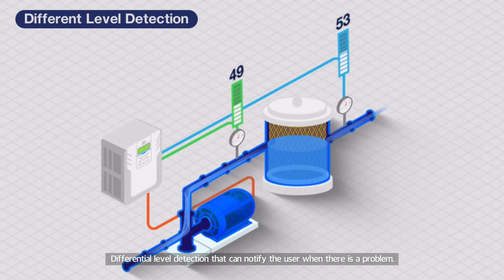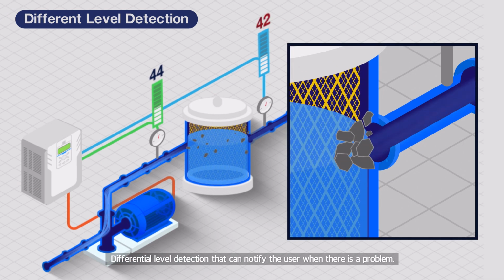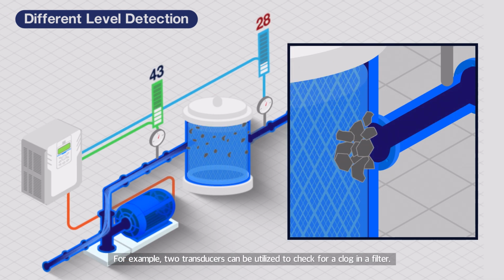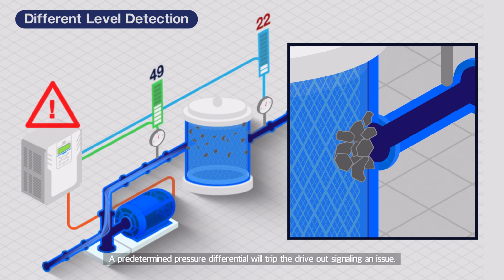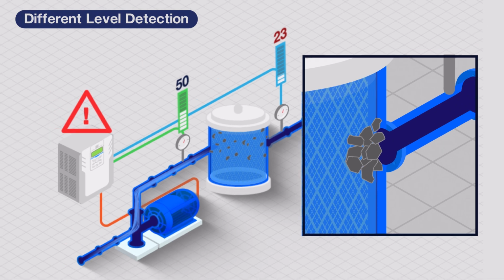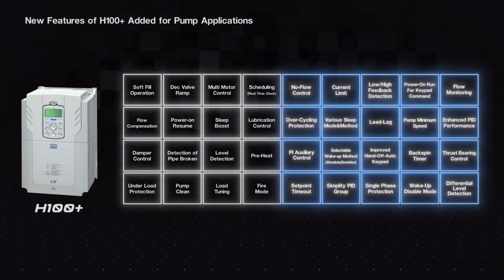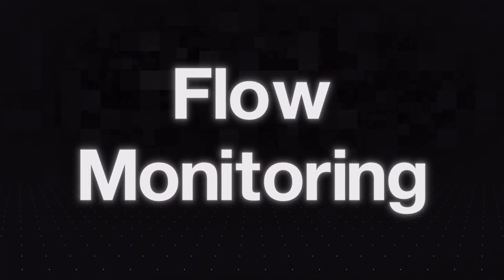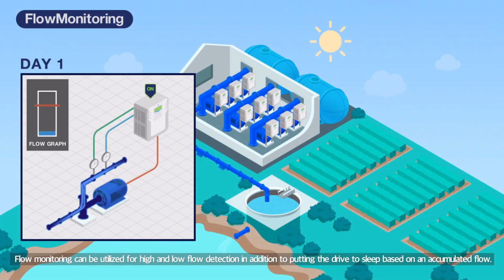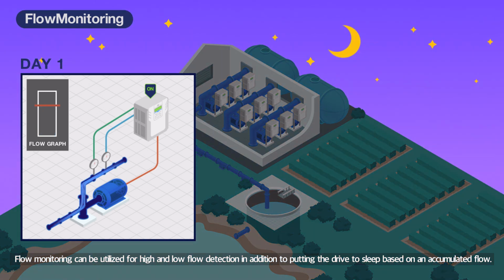Differential level detection that can notify the user when there is a problem. For example, 2 transducers can be utilized to check for a clog in a filter. A predetermined pressure differential will trip the drive out, signaling an issue. Flow monitoring can be utilized for high and low flow detection, in addition to putting the drive to sleep based on the accumulated flow.